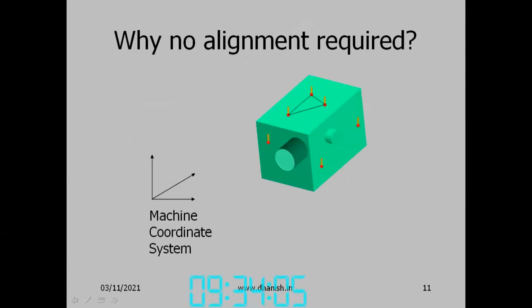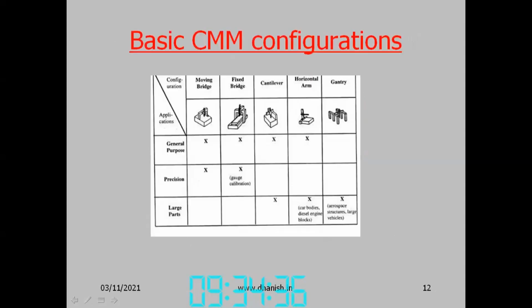So why is no alignment required? There is the machine coordinate system and the workpiece, and we want the measurements in the workpiece coordinate system. Once the relationship between the two is defined, so you define the workpiece with a 3-2-1 system like this, top 3, 2 on the left and 1 on the front side, then we can convert the coordinate system from machine coordinates to workpiece coordinates. So we don't need to align the workpiece. That's a big advantage of the CMM. So time is saved in the CMM.